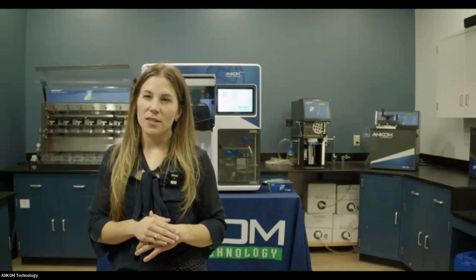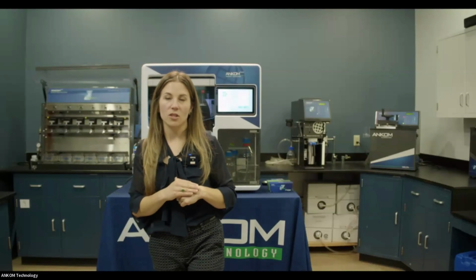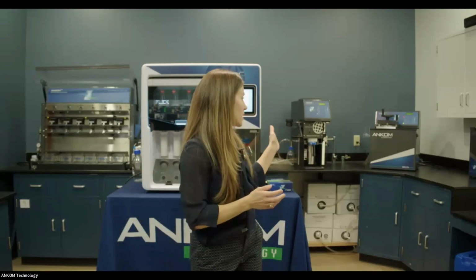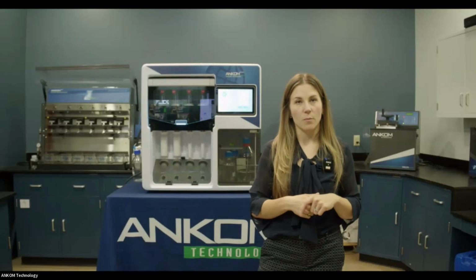I understand that from your presentation, the instrument is manufactured to extract fat from food to be ready to test in GC or HPLC. That is correct. So the Flex will extract the fat, it'll capture the oil for you, and you can then take that oil for further analysis on your GC or HPLC. If you use the XT15, this does not capture the oil for you. It is all done gravimetrically, or an indirect method. I would say the reason people will choose maybe the XT15 over the Flex is for its throughput and because they don't need to do that further analysis. If you need to do that further analysis, the Flex would be a better option for you.